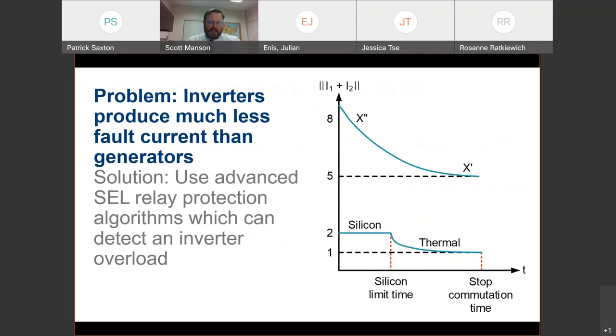The biggest one is right here, is that least cost inverters don't produce the level of currents needed to discriminate between a human being that's being electrocuted and normal load. And that's a major problem. That goes against all of the philosophies of the last 100 years of protection and control. Does it mean the day's over? No. It means that we have to get very sophisticated with protection to discriminate between life or environmental ending challenges and typical load behaviors. It means you need sophisticated algorithms in protective relays.